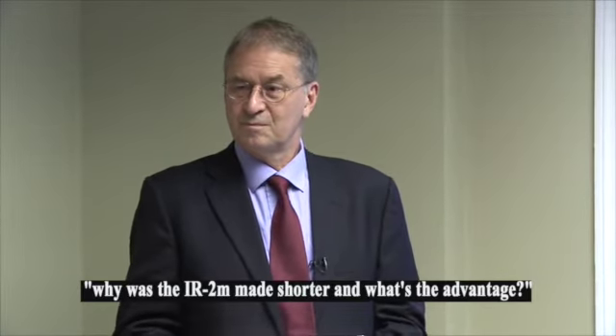We have one more question from Henry. Why was the IR2M made shorter? What's the advantage of having a shorter one, less moving parts, perhaps? Well, the bellows is a difficult part to make. On the IR1, the bellows has a smaller diameter and it's thicker, whereas on the IR2M it's wider and the walls are thinner, so it's a much harder bellows to make, and that's one of the reasons. The other is that any centrifuge is hard to get to work, and the IR1 is a proven design, and so they're in essence copying it, and they're having a lot of breakage.